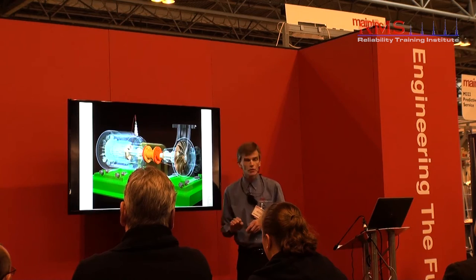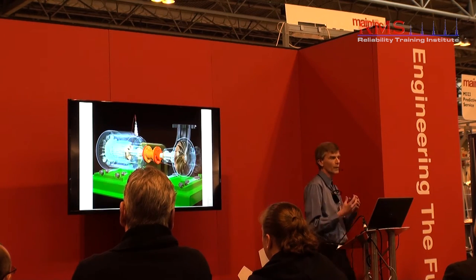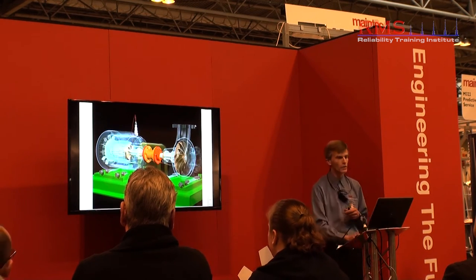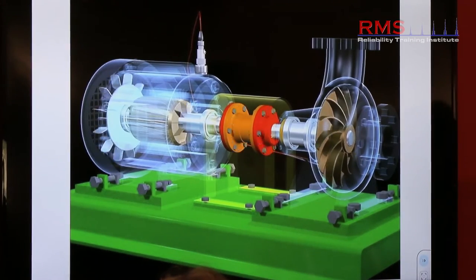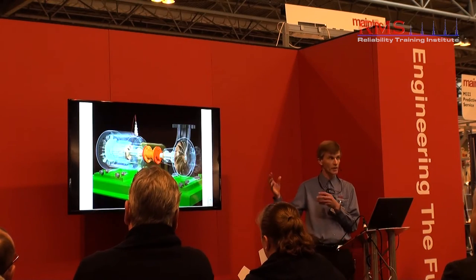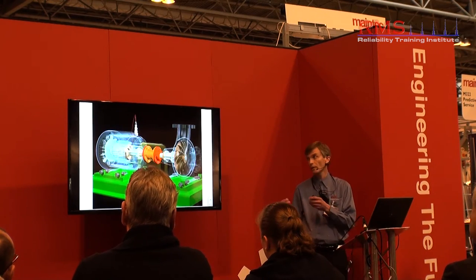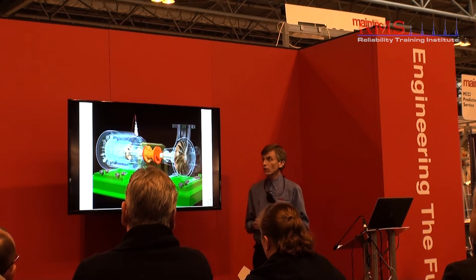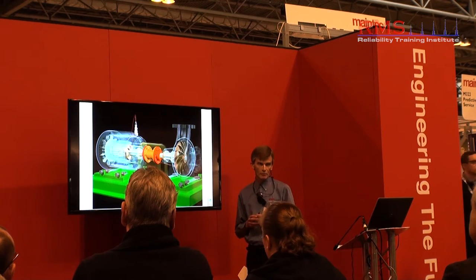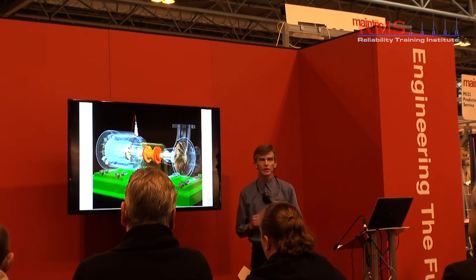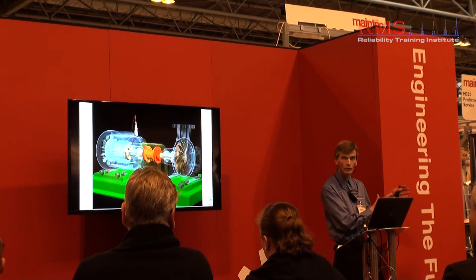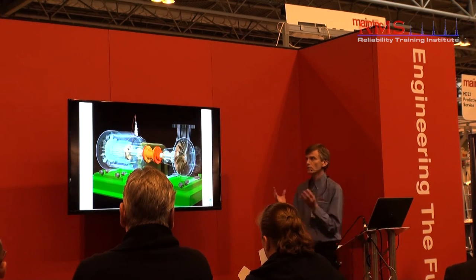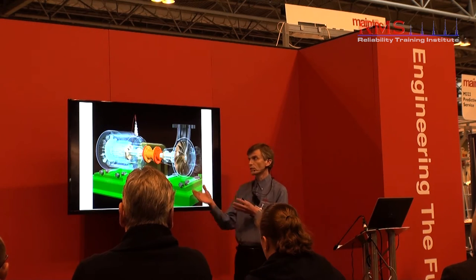Here we have a sensor placed on the machine. The forms of vibration that we measure at this particular location could be electrically related, they could be mechanically related to different parts of the machine itself, and thirdly, there could be a process vibration. Whenever we take a vibration measurement to track the health of an asset, all of those different considerations could be measured through the signal.